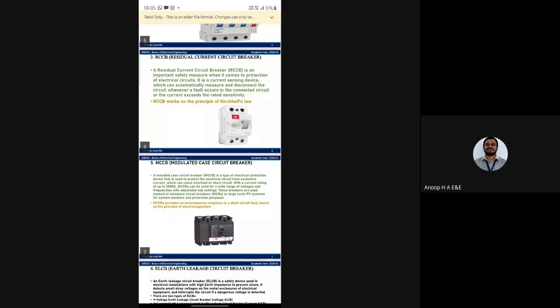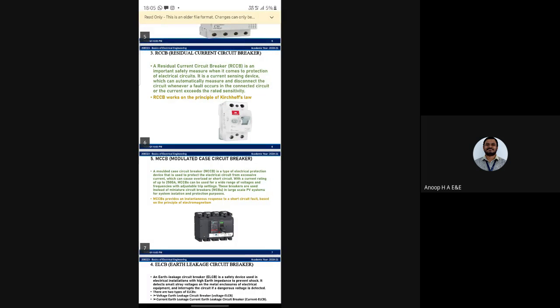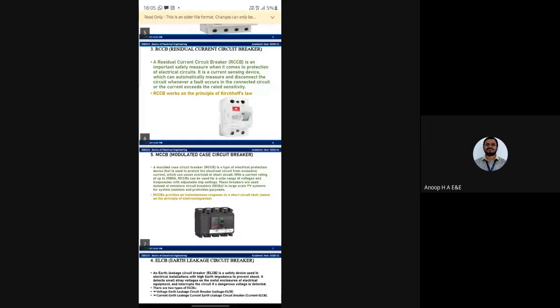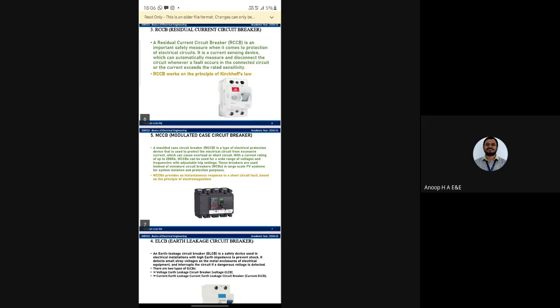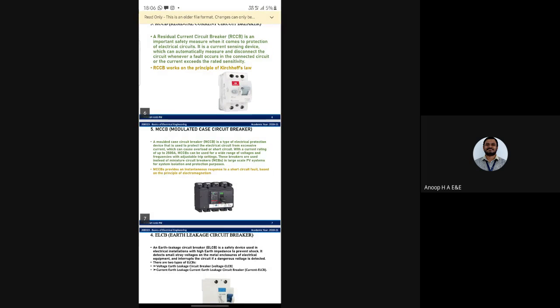RCCB. Full form of RCCB is residual current circuit breaker. A residual current circuit breaker is an important safety measure when it comes to protection of electrical circuits. It is a current sensing device which can automatically measure and disconnect the circuit whenever a fault occurs in a connected circuit or the current exceeds the rated sensitivity. RCCB works on Kirchhoff's law.